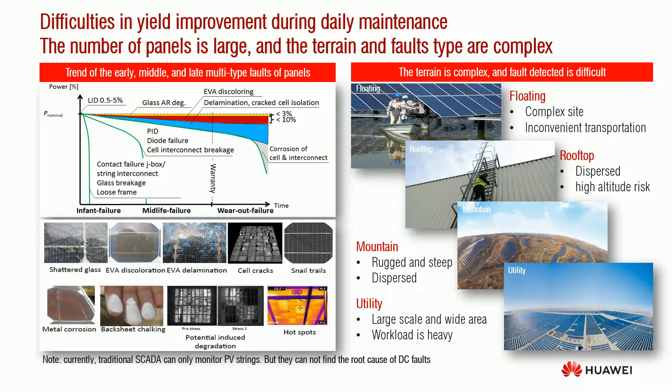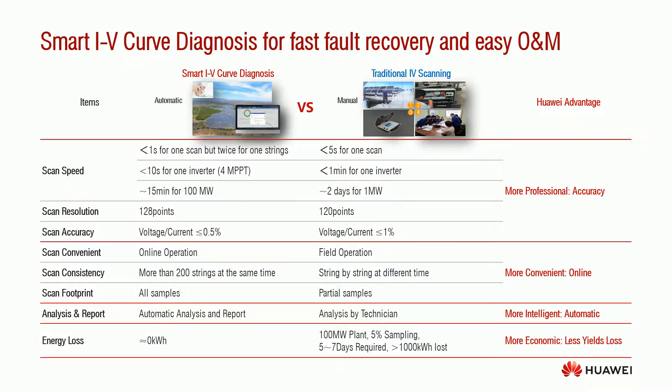Hotspots occur when shading or non-uniformity occurs on one module. This creates a very high reverse bias across a very small region, which causes high temperature and so-called hotspots. When the hotspots last for a period, the breakdown of a solar cell encapsulated inside the module occurs, which probably leads to fire.